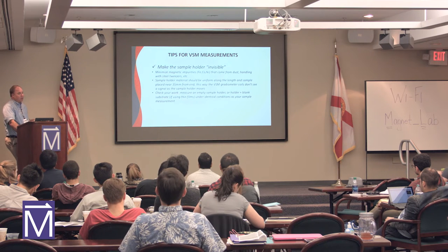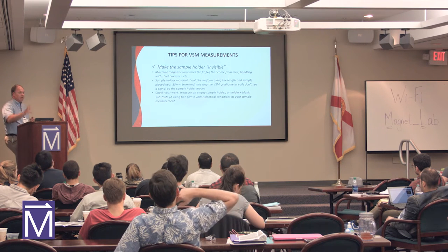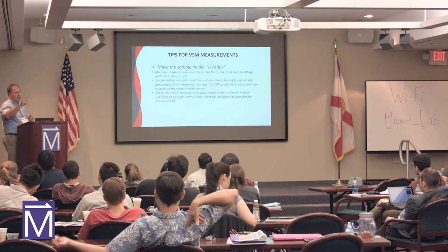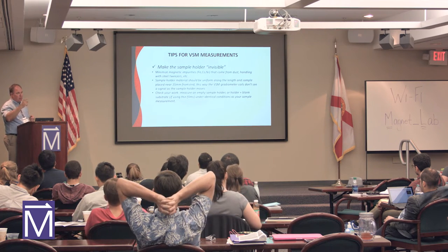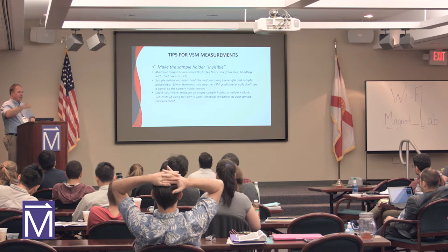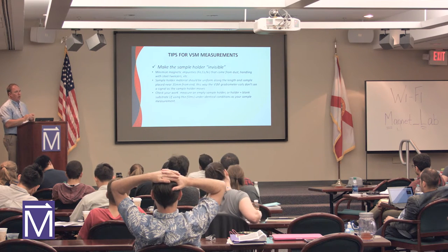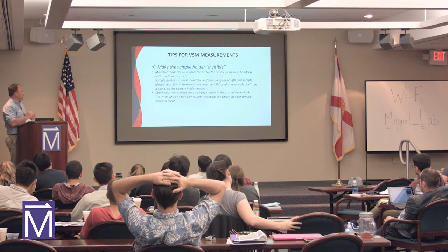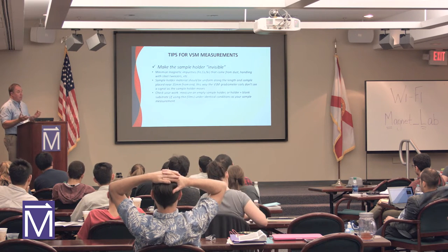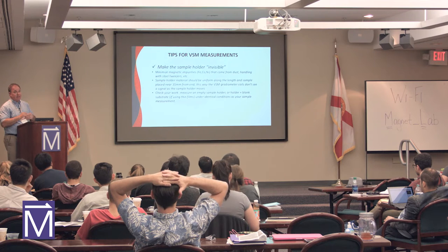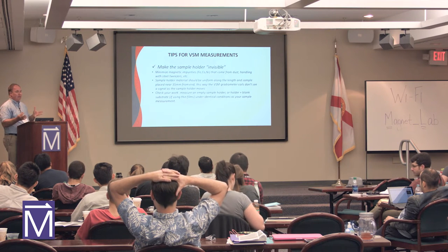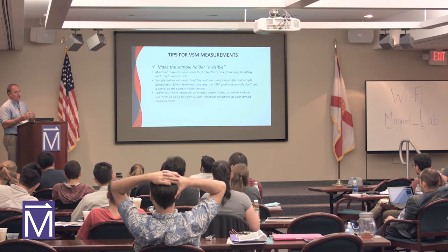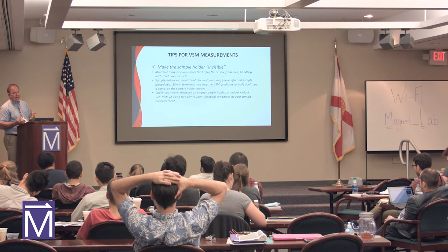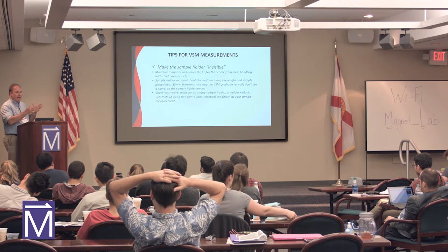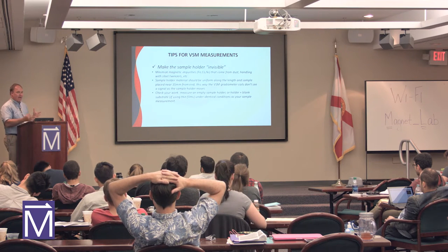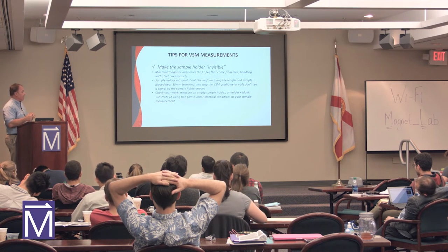Keep your sample holder uniform. The sample holder itself is long. You say, well, why don't you just make the sample holder small and put it in there? Because you want the sample holder to be constant as it's going through the coil set, so the sample holder isn't inducing anything into the coil set. So your sample holder material should be non-magnetic. If you have a new set of straws, say somebody changes the straws, run the blank straws, run your blank holder. Do I have an artifact of my sample holder? Is that causing some artifact in my VSM measurement?